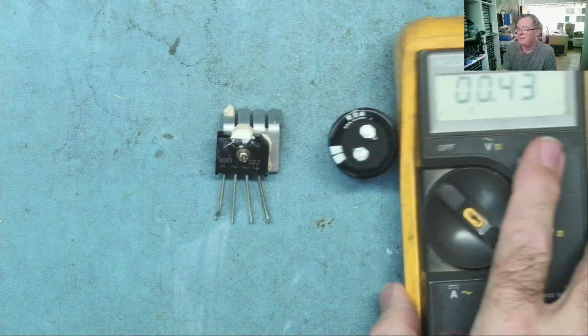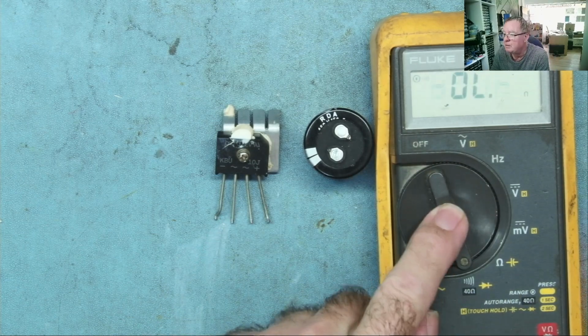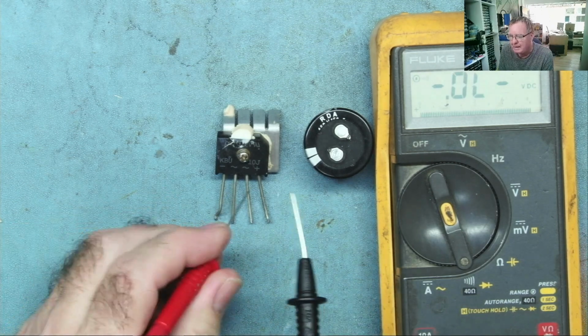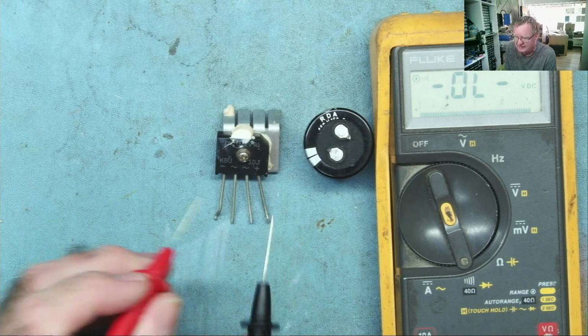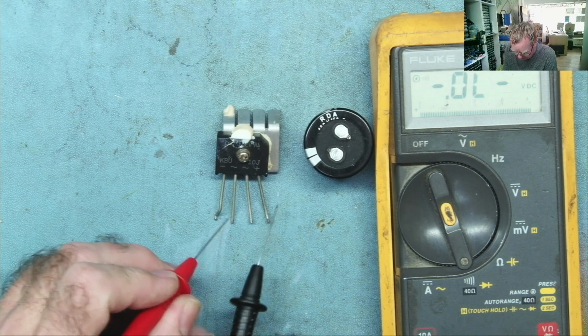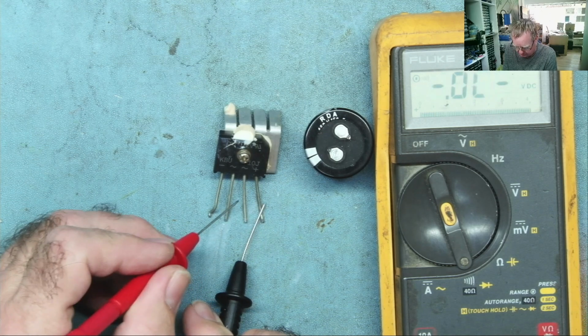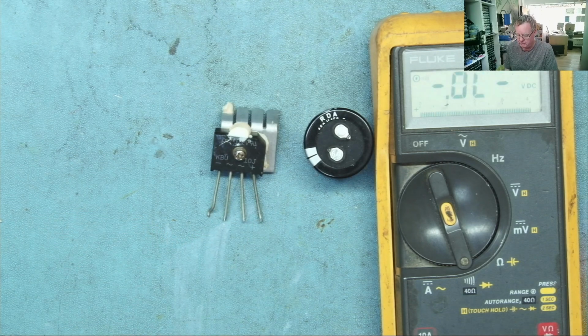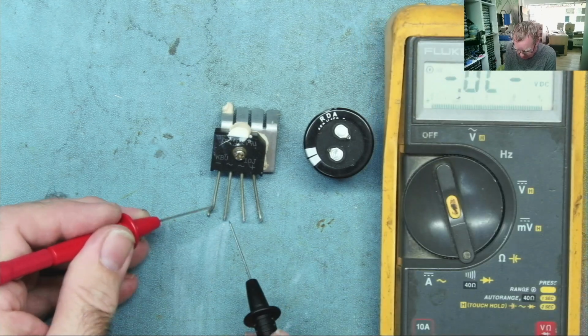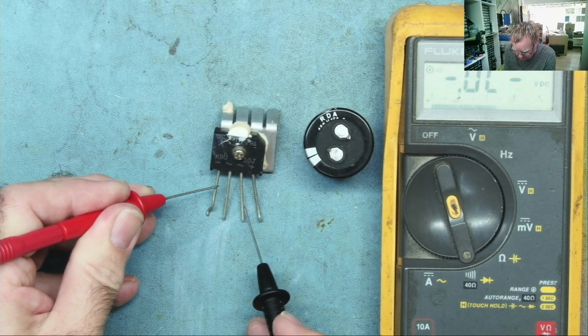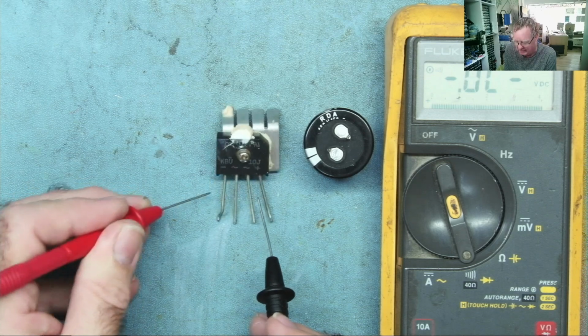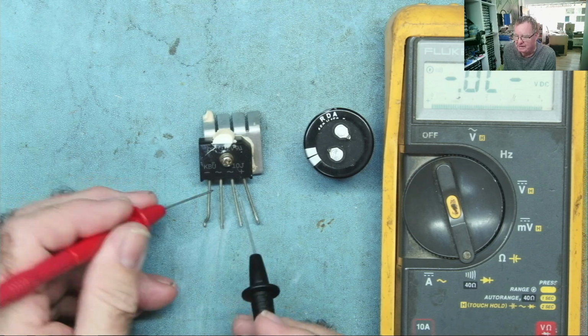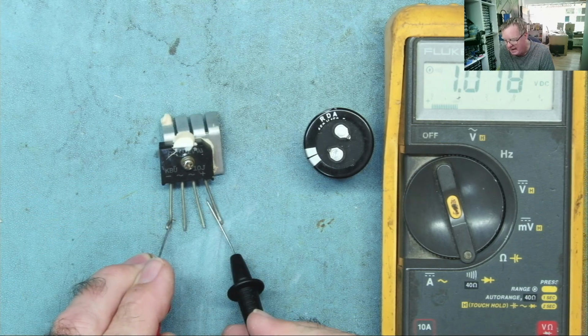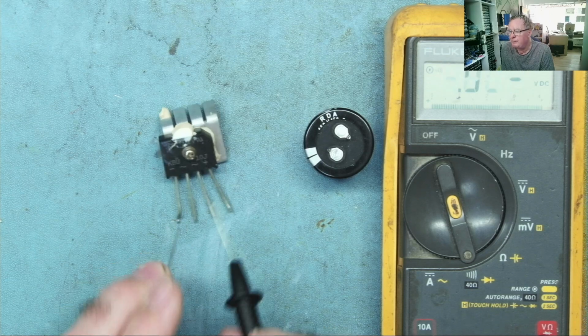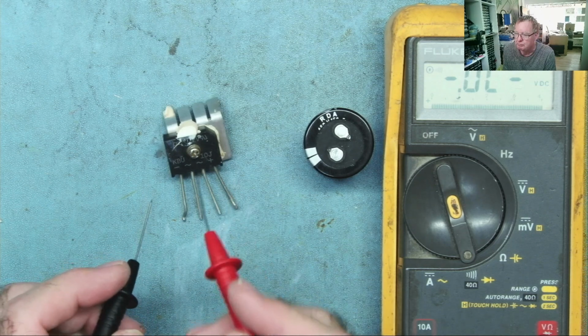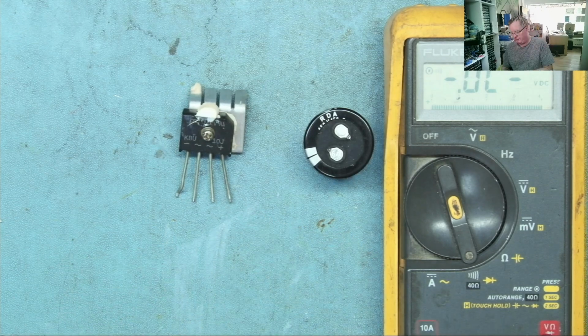The bridge rectifier is easy to test as well. We go to diode mode, and if we put the red lead on both of the AC terminals, we should see a diode junction to the positive - black on positive, red on AC, there's a diode junction, and then the other way around with black on the AC, red on the minus terminal, diode. And across the bridge rectifier itself in the reverse direction, with red to the negative, we'll see like two diodes in series - roughly two diodes in series, 450 times 2. And the other way around, with red to the positive, it will read open. So the bridge rectifier is good, the capacitor is good.